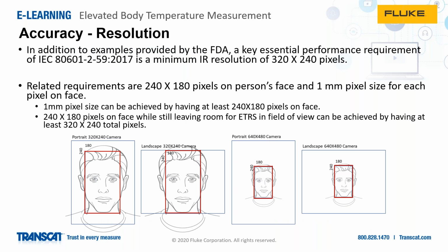So, the next piece on accuracy that makes sense to talk about here is the resolution of the camera that's being used. In addition to the examples provided by the FDA, a key essential performance requirement from this IEC 80601 standard is to have a minimum IR resolution of 320 by 240. And we've shown some portrait and landscape views of 320 by 240 cameras, as well as 640 by 480 cameras, to give an idea of how much the face might fill of that camera, depending on what distance they're standing away. But the related requirement here is that you have at least 240 by 180 pixels on the face to get a 1 millimeter pixel size for each pixel on the face. And we'll talk a little bit more about why the 1 millimeter pixel size, but that's what can be achieved by this 240 by 180.